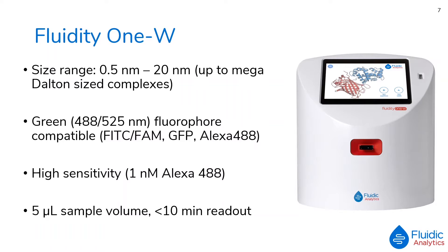The size range the Fluidity 1W is able to measure is between 0.5 nm to 20 nm. This range covers most small molecules and dipeptides all the way up to approximately 15 megadaltons, so almost all the protein species that might be found in a cell. It is compatible with green fluorophores including FITC, GFP, or Alexa 488 equivalent dyes. High sensitivity means that KD values for binding interactions in the picomolar range can be measured. Importantly, these measurements are carried out fully in solution with no surface fixing, using just 5 microlitres per sample.